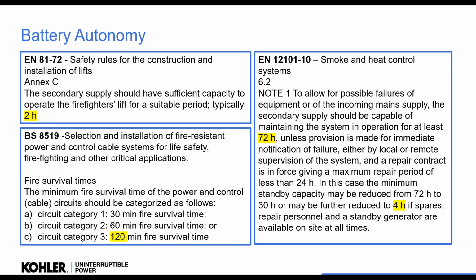Different regulations have different requirements, and it is up to your application and the regulations you are using to be able to define that. So, 8172 for lifts, typically 2 hours. 8519, 2 hours. But there's some smoke and heat control systems that part of it needs to be maintained for 72 hours. Now that might well be a case you put a separate battery in for that part, just running that part, and then have the UPS for the minimum standby times.